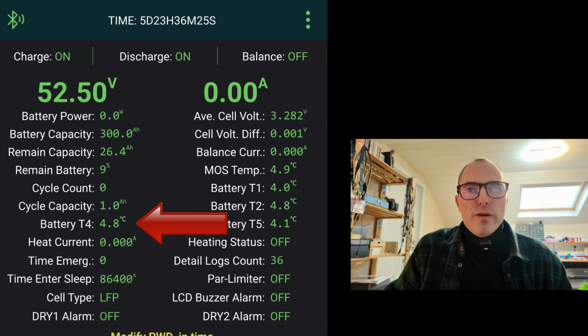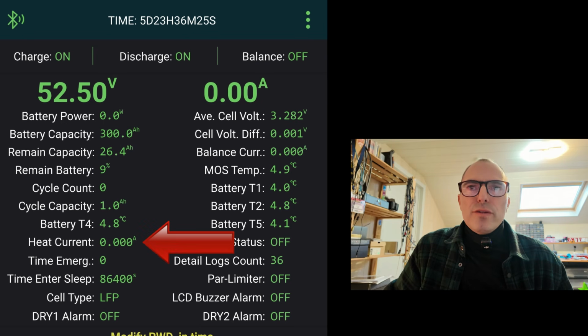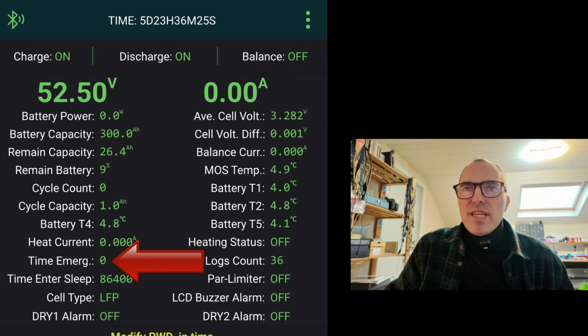Battery T4 is one of the 4 temperature sensors. Heating current is the current for the heat pad, if it's connected. The maximum current is 3 amp. If connected to a 55 volt battery pack, we're over 150 watts. Time emerge is the time the emergency setting remains active. I think it's standard 1800 seconds, so 30 minutes.